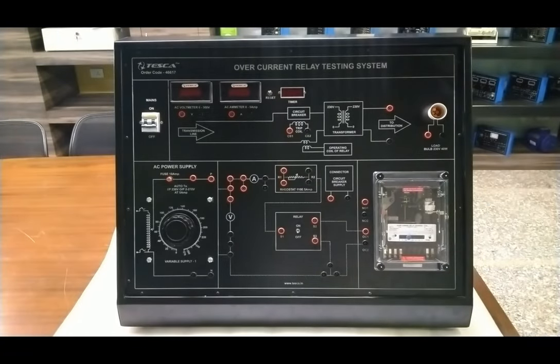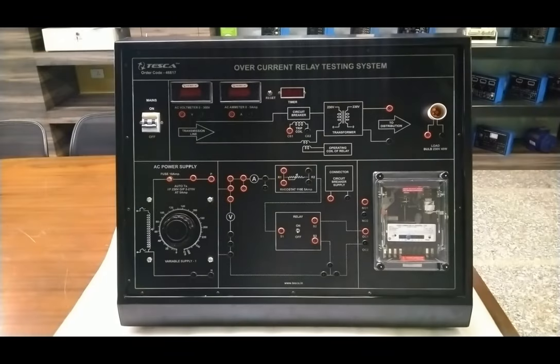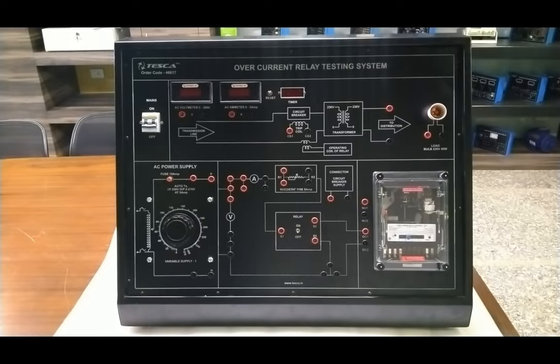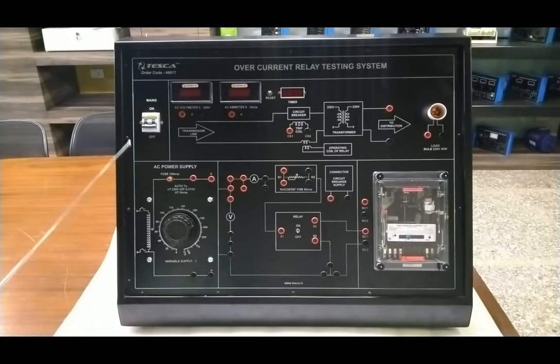This is the overcurrent relay testing system complete trainer board you are seeing on your screen. The overcurrent relay monitors general balance, overloading, and has current and time settings — these settings determine the protective schemes. The relay is IDMT type, which has different tripping times and characteristics. We will explain all the system parts one by one. We have a mains on/off MCB here.